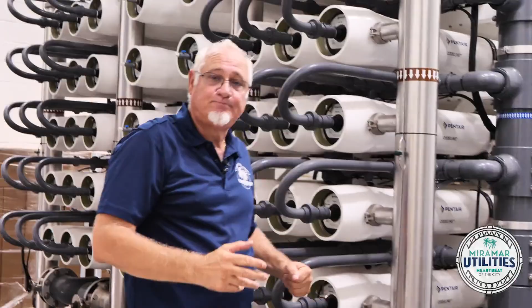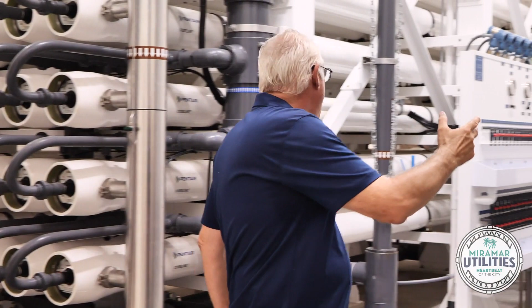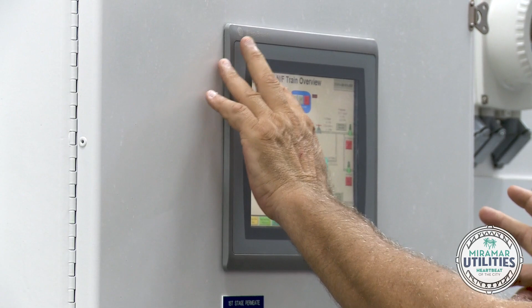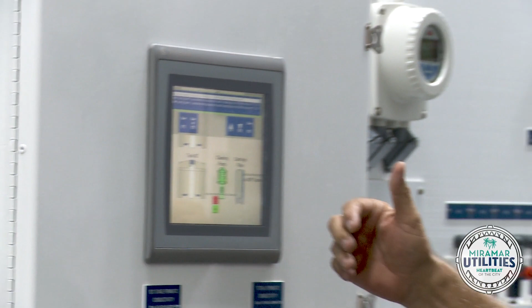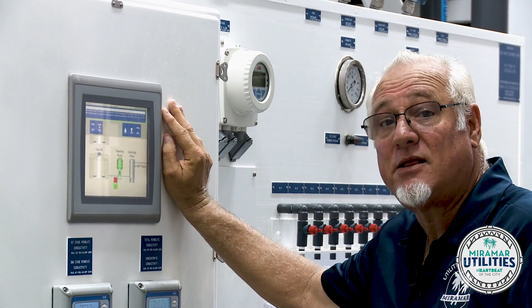During that time, we control it using a human machine interface, a touch screen - this is what we call an HMI. We use it to wash the system and regenerate it. We can go through and check all the equipment and operate it from here, but this is just for on-site operations. Most everything is run by our SCADA system, either automatically or manually operated by our operators in the control center.